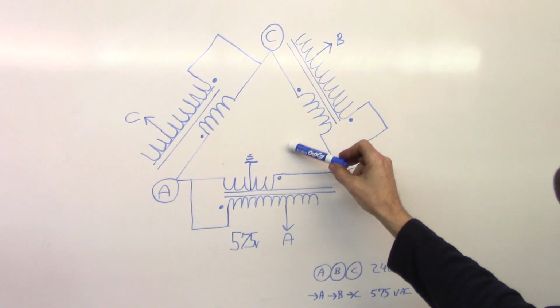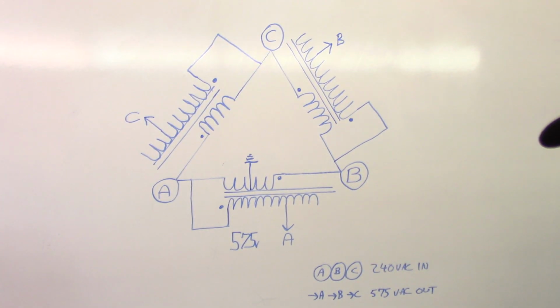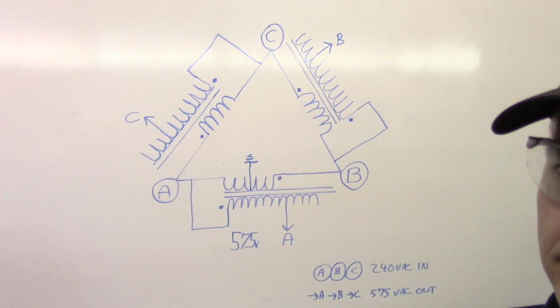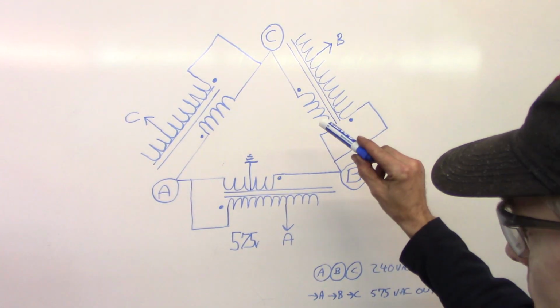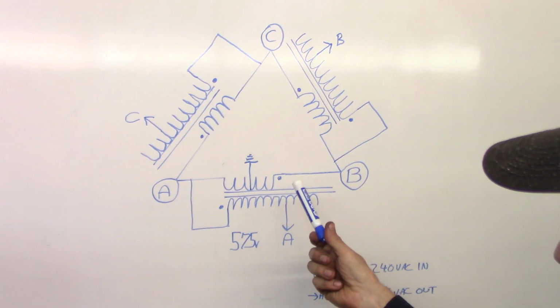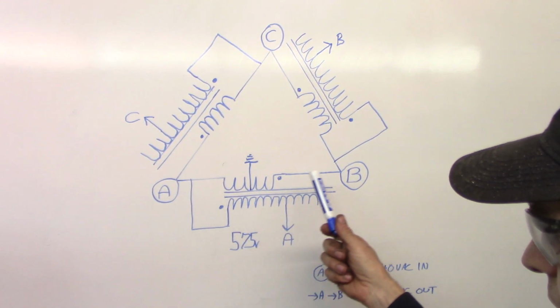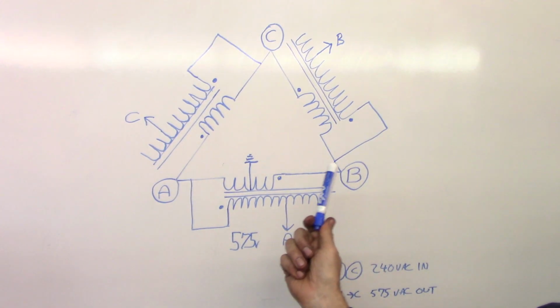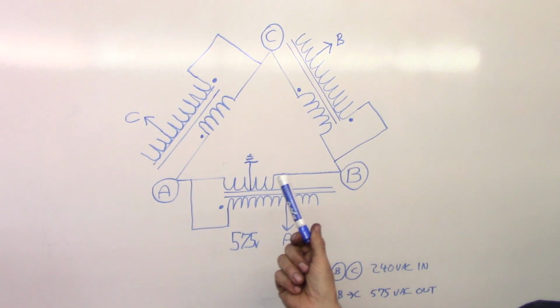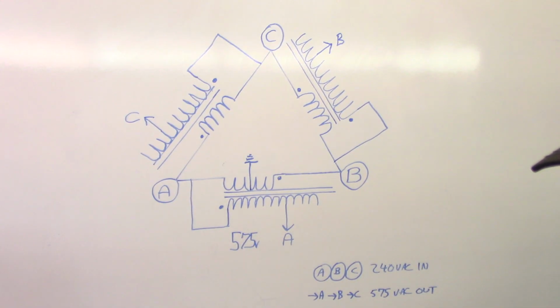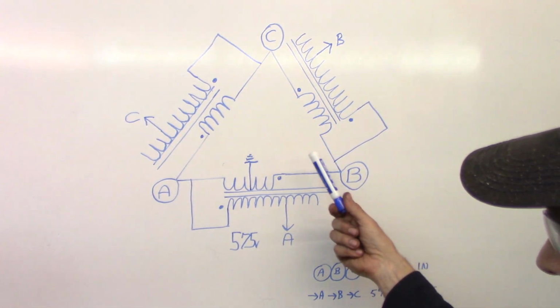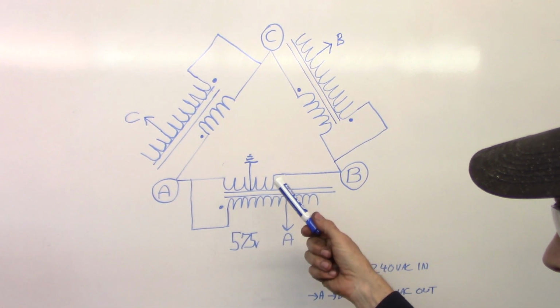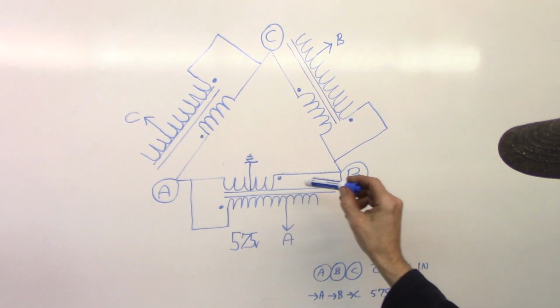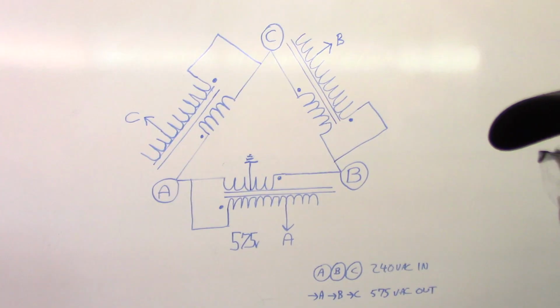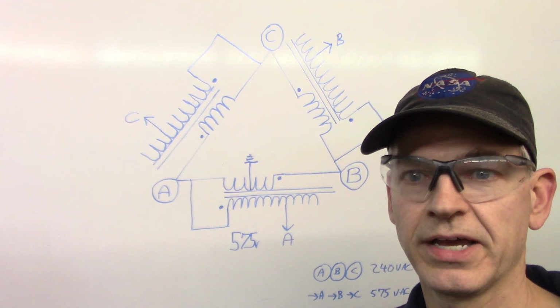This isn't exactly like I've shown it in any textbook or anything I found on the internet, but it's just taking the concept of a single phase auto transformer—wiring an isolation transformer as an auto transformer, in boost mode as opposed to buck mode. That's all it is. And because delta preserves the voltage, I can use 3 of them at the 240 designated voltage without any issue, none of this Y stuff.